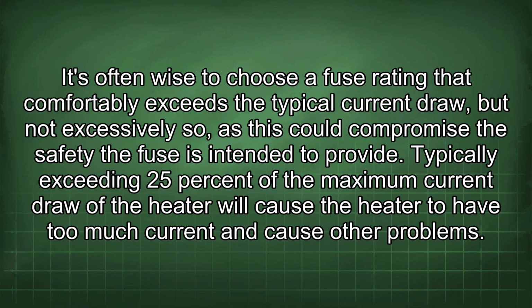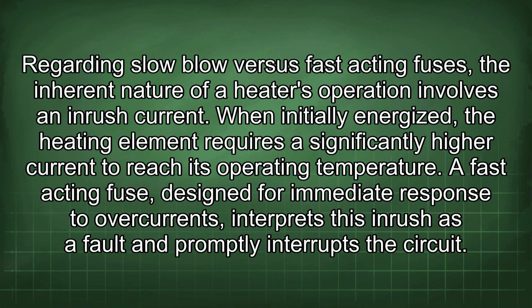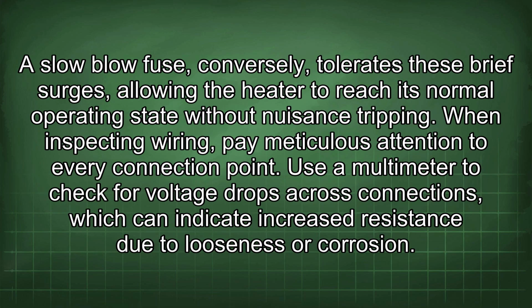Typically, exceeding 25% of the maximum current draw of the heater will cause the heater to have too much current and cause other problems. Regarding slow blow versus fast-acting fuses, the inherent nature of a heater's operation involves an inrush current. When initially energized, the heating element requires a significantly higher current to reach its operating temperature. A fast-acting fuse, designed for immediate response to overcurrents, interprets this inrush as a fault and promptly interrupts the circuit. A slow-blow fuse, conversely, tolerates these brief surges, allowing the heater to reach its normal operating state without nuisance tripping.